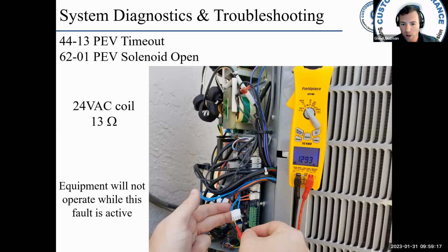If you read OL when you put your meter leads there, then hey, I've got an issue with the solenoid. I would check the wires, of course, get the solenoid in your hand and physically look at it. Is it hot? Is there some reason why it opened? Maybe a wire got pinched. But the equipment will not operate while that fault is active.